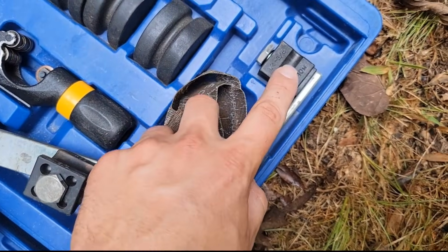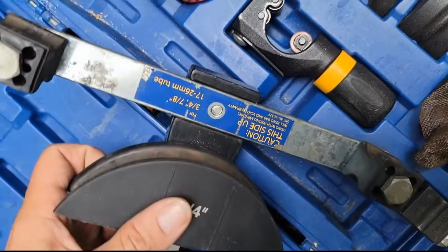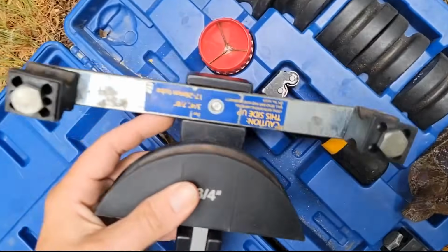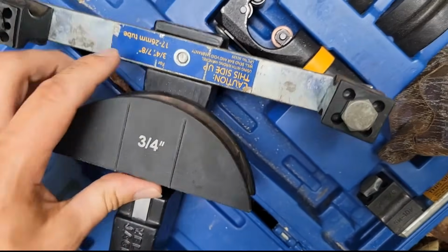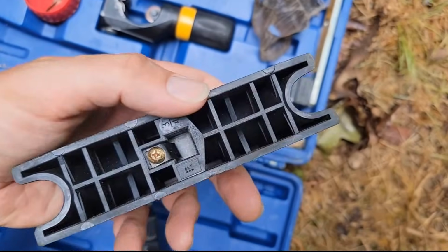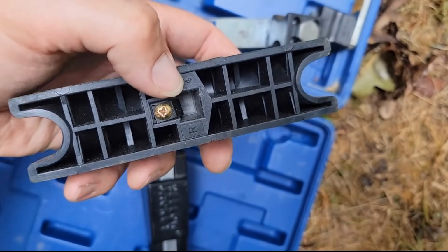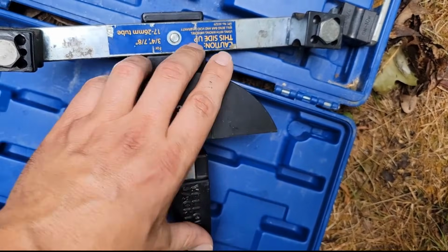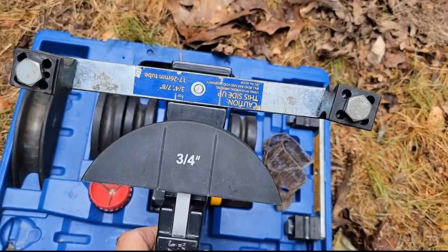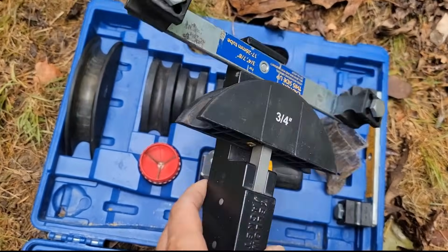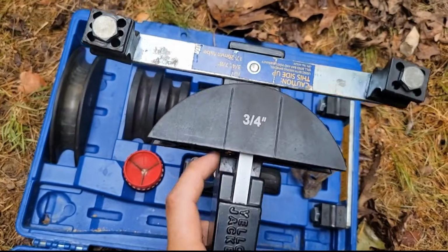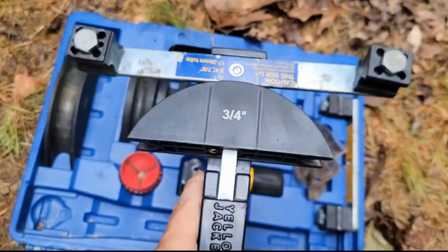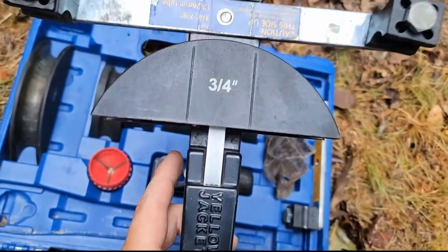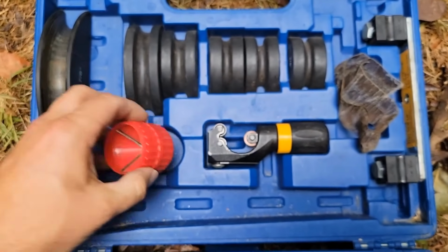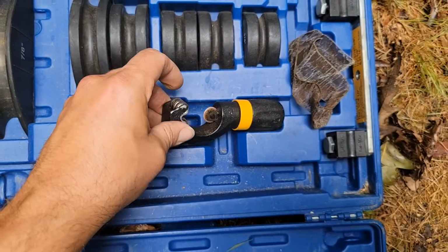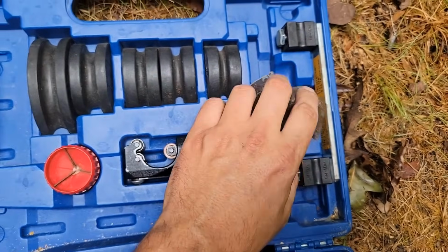You got 2 bars here, one for 1/4 inch to 3/8, and then this one's from 3/4 to 7/8. You take the bar, you use the wing nut, and you screw that bar in. And then this right here is for 3/4, and you just take it and you slide it on. Willie says you need to make sure that you tighten the Phillips screw because otherwise it just doesn't work as good with 7/8. So 3/4, he said you don't have to tighten that Phillips screw, but with 7/8 it may come off. You want it to work as best as possible, so tighten that Phillips screw. This kit comes with a little reaming tool, deburring tool, and also with a pair of tubing cutters. Sandpaper, nice.